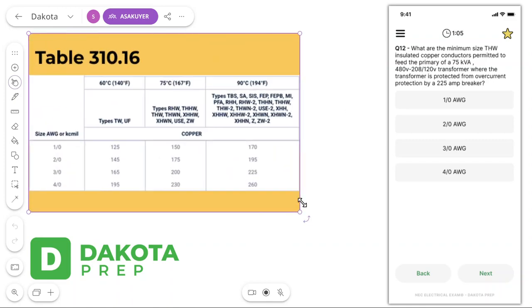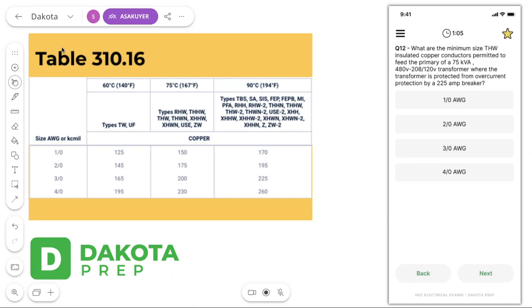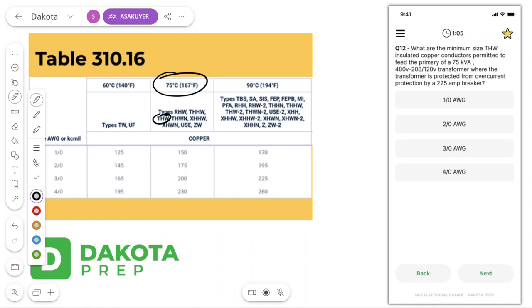We cruise to everyone's favorite table, the infamous and famous Table 310.16. It says we've got THW conductors. We go find THW conductors. Okay, turns out right here, THW conductors are rated for 75 degrees Celsius. We're in a 75 degree column here, 75 degree column. Are they copper or aluminum? It says we've got copper conductors. Okay, we are in fact in the copper columns, the three copper columns section, right, with aluminum and copper clad being toward the right on Table 310.16. So we're in our 75 degree column of our copper columns, right, because we have THW conductors.